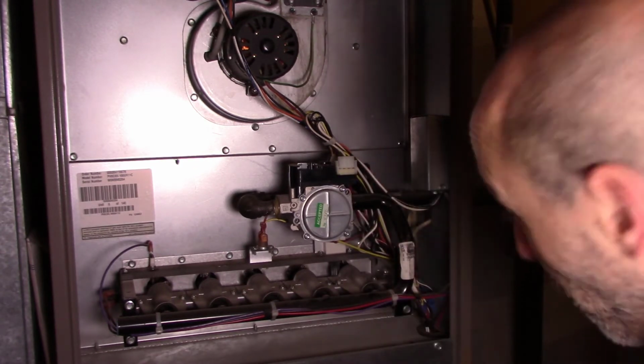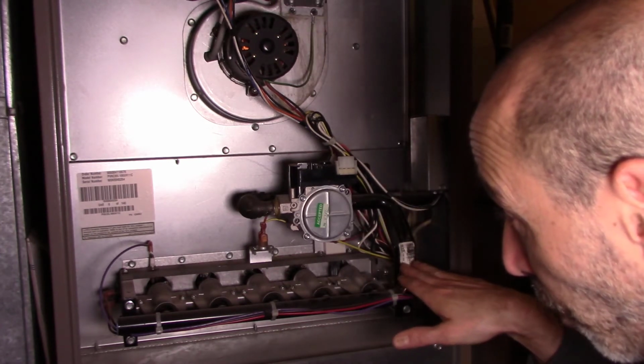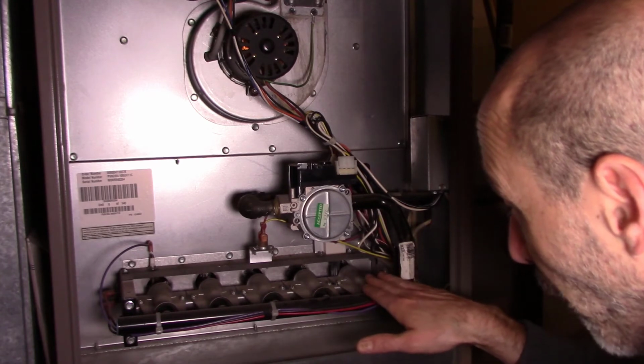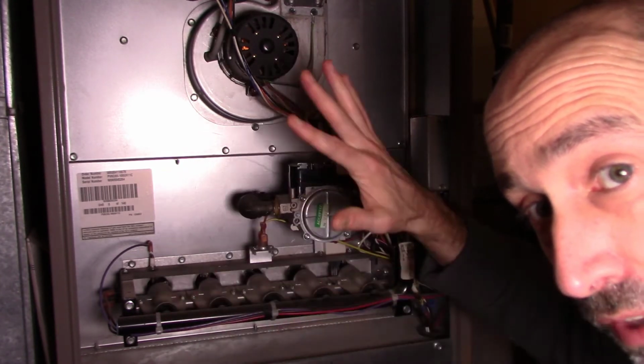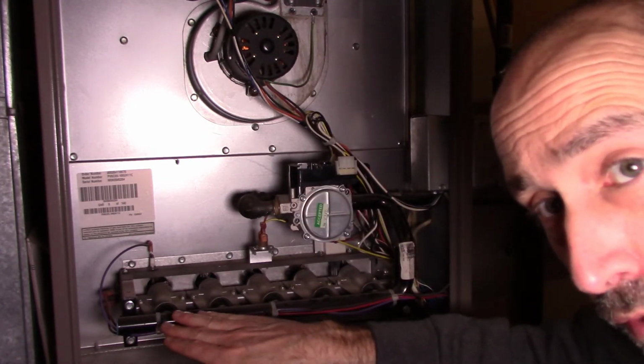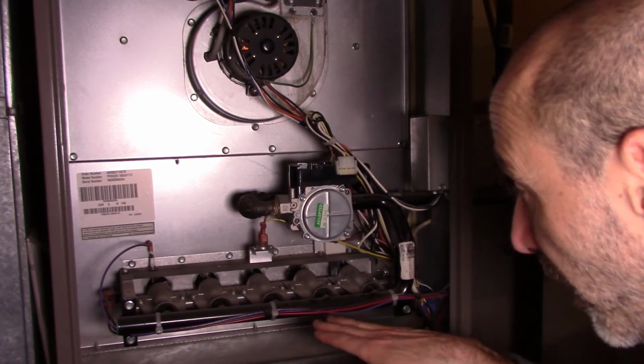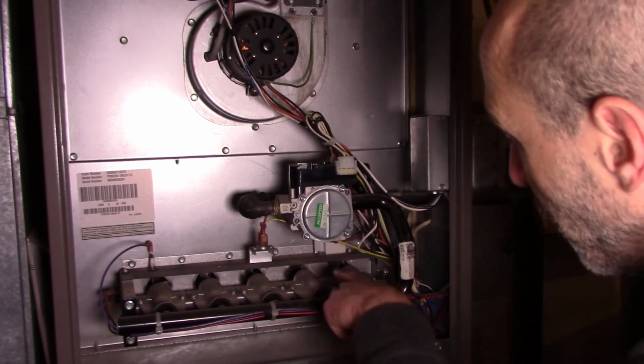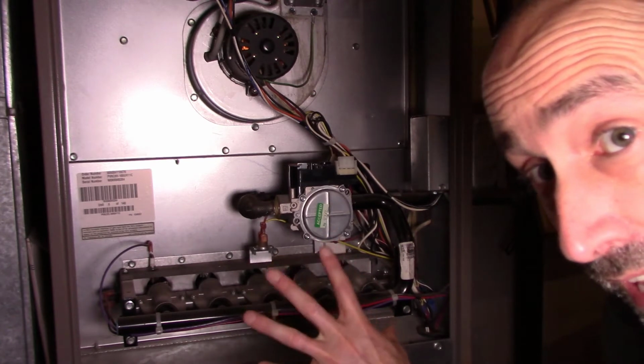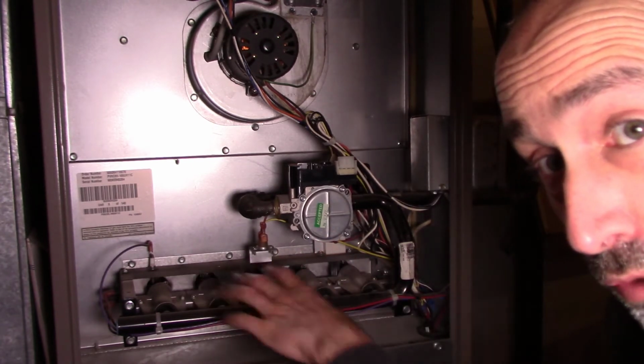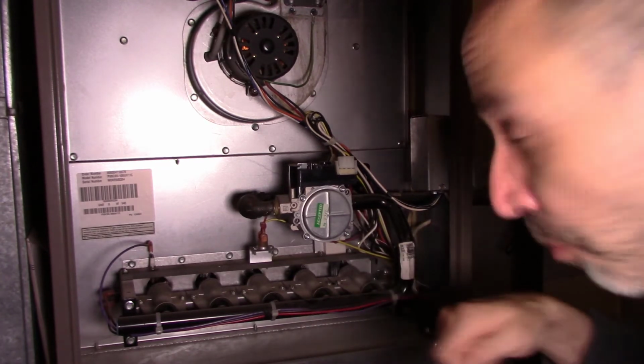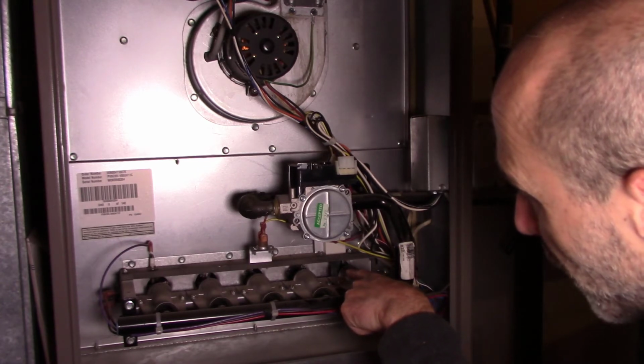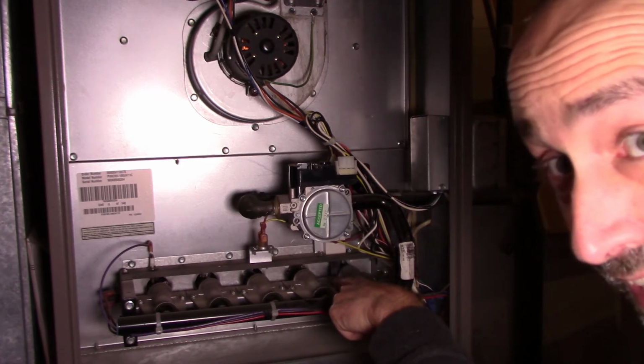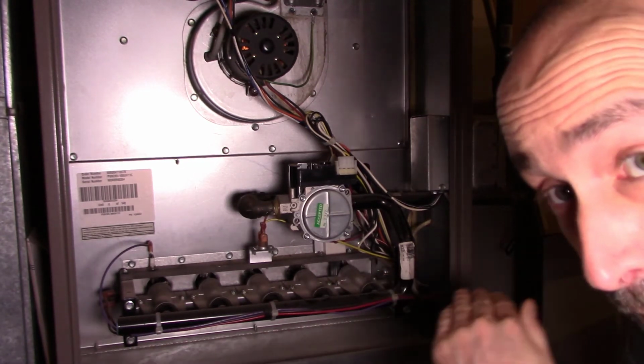Okay, so now we've got past that. We've got glow, and then we have ignition. Another very common problem is you'll get ignition, the flame will ignite this burner, but let's say the fire doesn't spread all the way to this last burner, and then everything shuts off. If you don't see the fire spread across the burners within a second, then it might likely be these burners are dirty. Typically, if you can, take these burners off by undoing those screws and clean them out with a nylon bristle brush. These burners are shaped such that when one burner fires, the fins spread the flame to the next one, and if those fins get dirty or clogged up, the flame may not spread across. So that's just a matter of cleaning these little burners off.